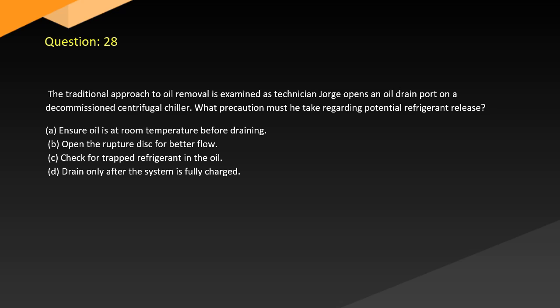Question 28. The traditional approach to oil removal is examined as technician Jorge opens an oil drain port on a decommissioned centrifugal chiller. What precaution must he take regarding potential refrigerant release? A. Ensure oil is at room temperature before draining. B. Open the rupture disc for better flow. C. Check for trapped refrigerant in the oil. D. Drain only after the system is fully charged.